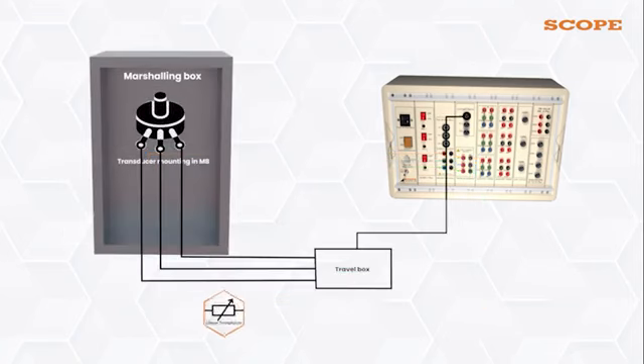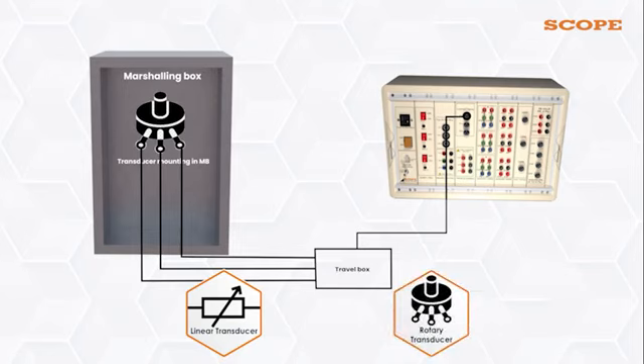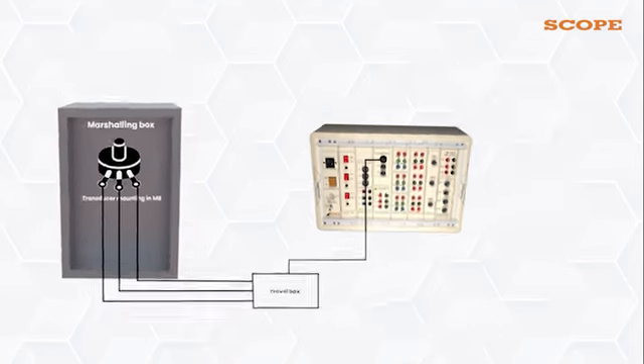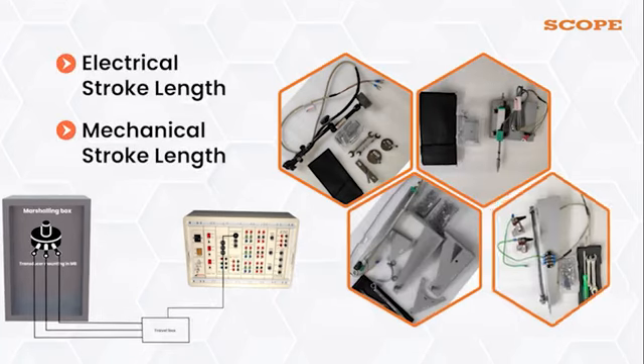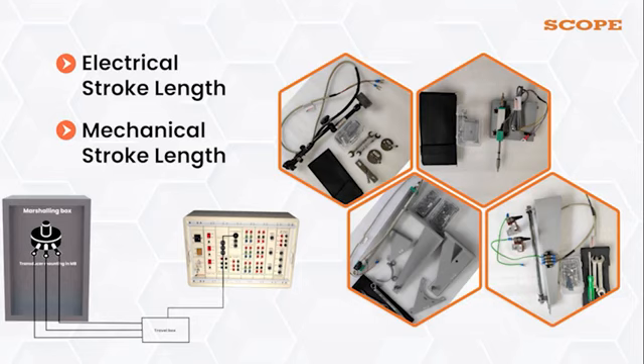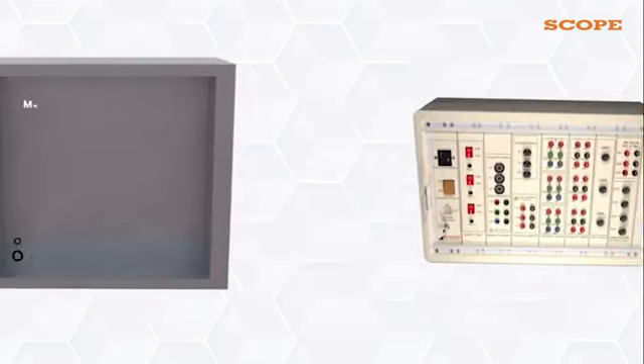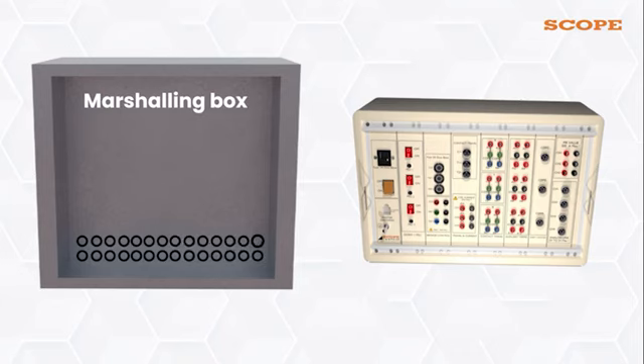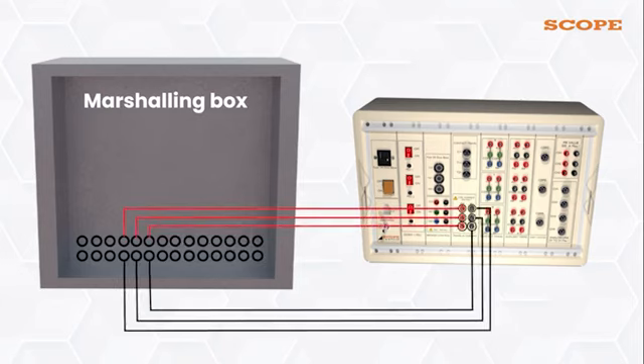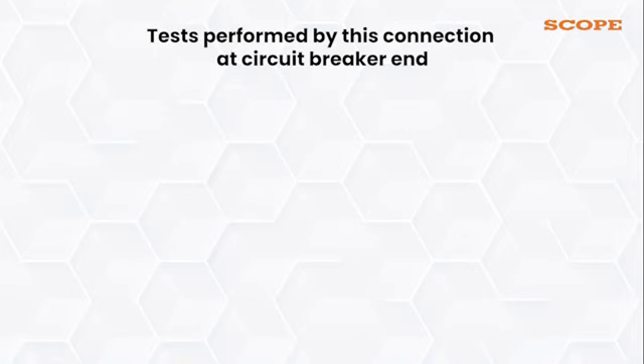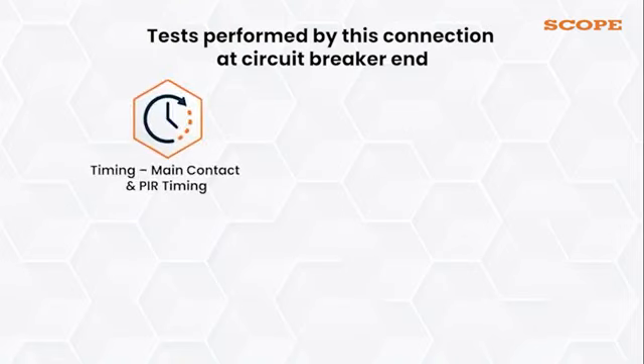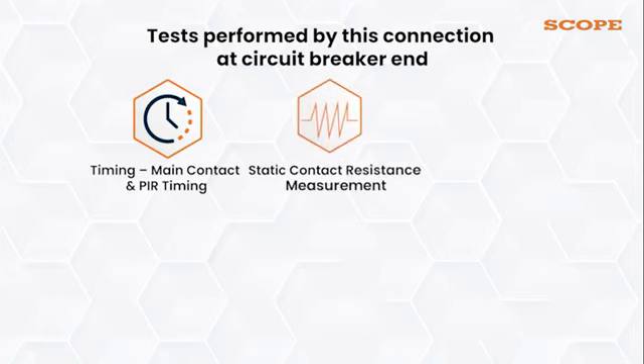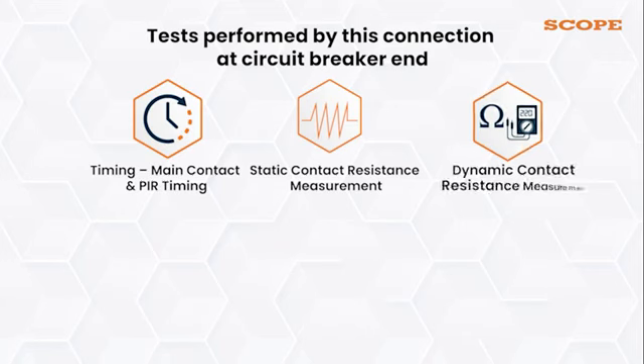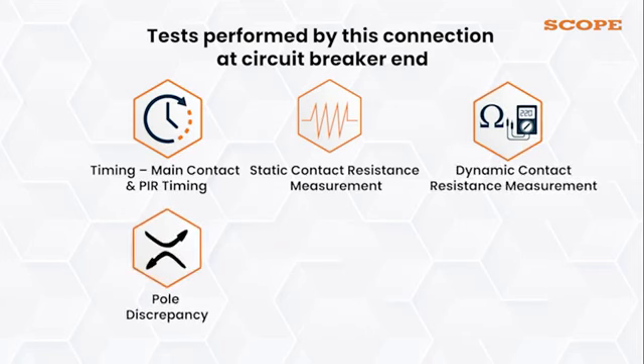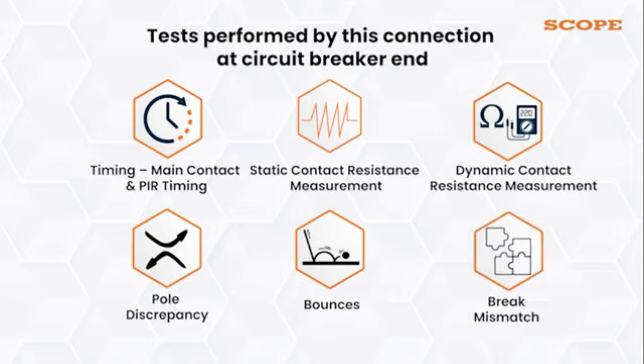Some breakers require the linear transducer, whereas some require the rotary transducer. This helps in calculating the electrical stroke length and mechanical stroke length of the breaker contacts that have moved. Let's continue to connect the travel and coil current at the marshalling box. The above figure shows the connection of coil current. Let's see which all tests are performed by this connection at circuit breaker end: timing, main contact and PIR timing, static contact resistance measurement, dynamic contact resistance measurement, pole discrepancy, bounces, and break mismatch.